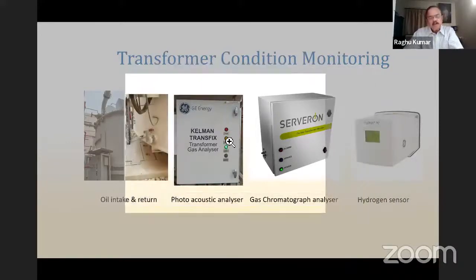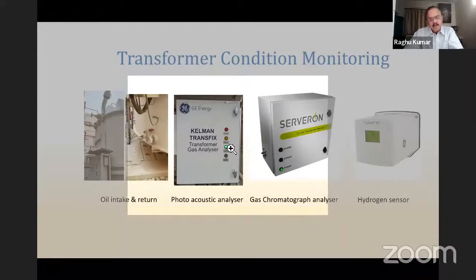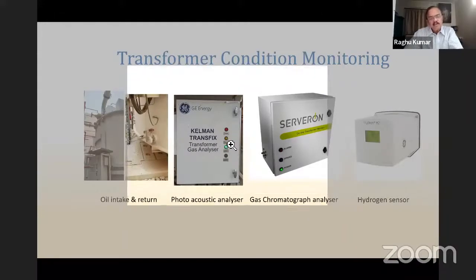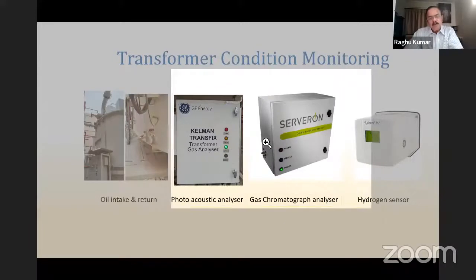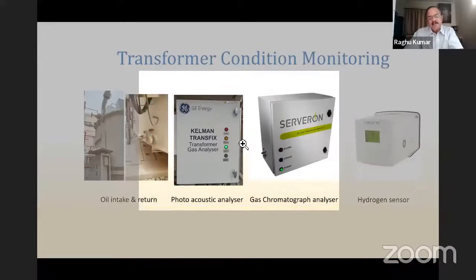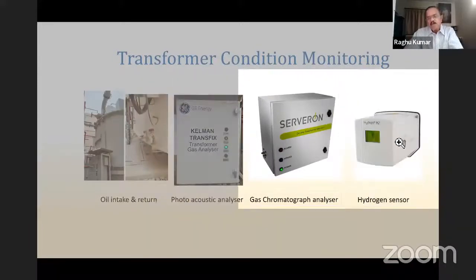This equipment does not require any calibration. It works on a photoacoustic analyzer, and there is no carrier gas involved in this. Both these equipments can get 9 gases checked. In smaller transformers, we fix hydrogen sensors. This can monitor only hydrogen and moisture. Most of the faults have hydrogen in them.